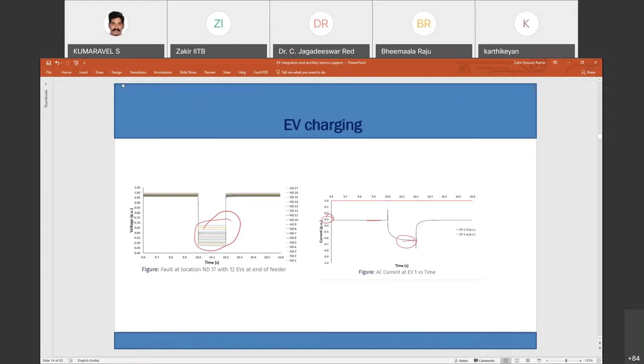Just a bit of the dynamics of it: we introduced a fault in the distribution feeder, and this is the current drawn by the electric vehicle. You can see initially it was 0.3 charging, and now it hit 0.6 charging. The reason is we had treated this EV as a constant power load in this case, so it was not constant current charging.